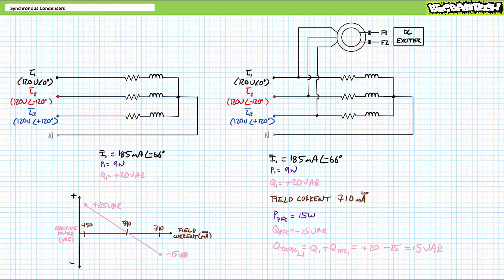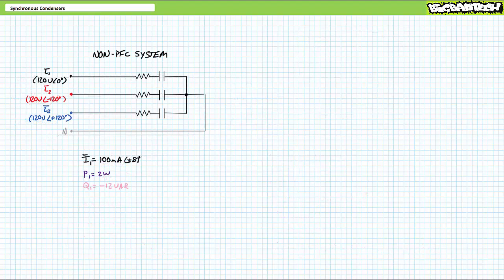Source current — the summation of load and synchronous condenser current — now only slightly lags supply voltage, not nearly as much as the non-power factor corrected scenario. In addition to synchronous condensers with over-excited rotors acting like capacitors and supplying negative reactive power, synchronous condensers with under-excited rotors can act like inductors and consume positive reactive power. This is the rarely exploited left half of the reactive power as a function of field current plot.